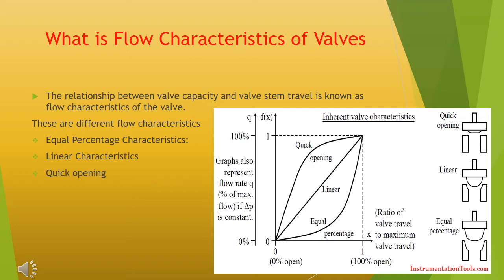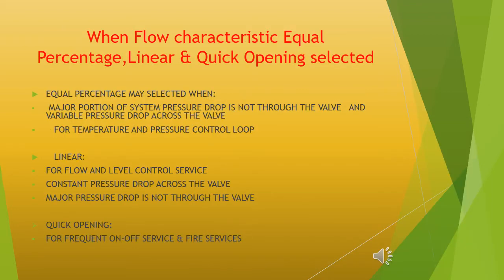Quick opening has too high a valve gain for use in modulating control, so it is limited to on-off service. When selecting flow characteristics — equal percentage, linear, or quick opening: equal percentage may be selected when a major portion of system pressure drop is not through the valve and there is variable pressure drop across the valve, for temperature and pressure control loops. Linear is used for flow and level control service with constant pressure drop across the valve. Quick opening is used for frequent on-off service and fire services.